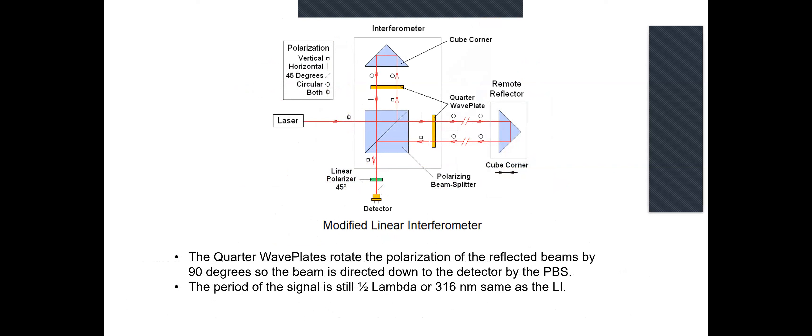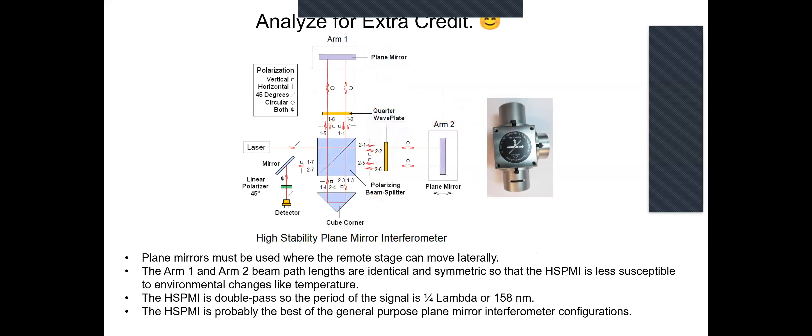The configuration you're using is very similar, but instead of mirrors, it uses cube corners. Therefore the quarter wave plates redirect the beam from traveling in the left-hand direction straight through the PBS to being reflected down to the detector. And that was simply done as a convenience in setting up the mechanical arrangement. It doesn't change the resolution, while the high-resolution high-stability plane mirror interferometer doubles the resolution because the light takes two passes through all the optics because of the quarter wave plates redirecting the beams. You can trace them yourself and figure out how it works.